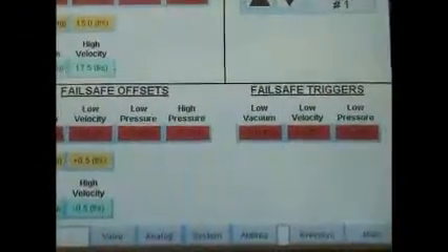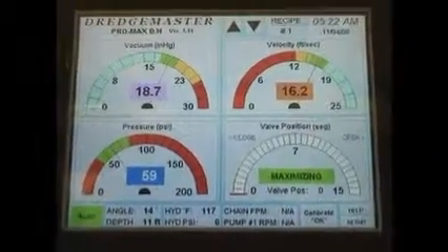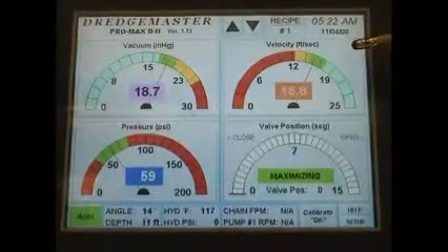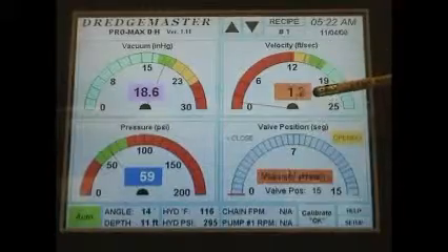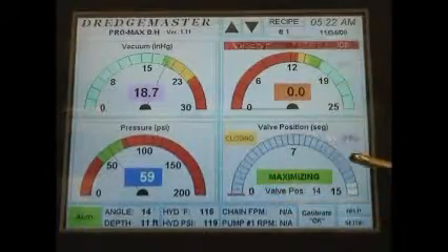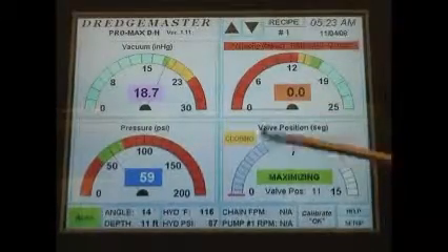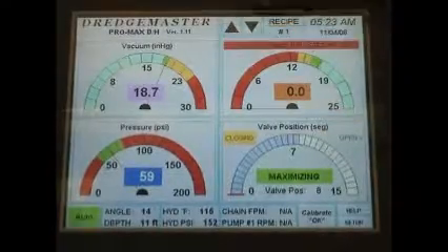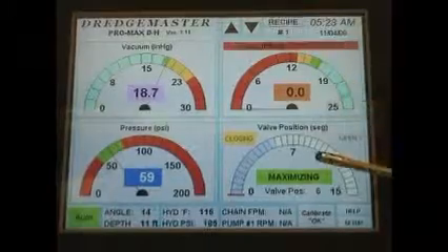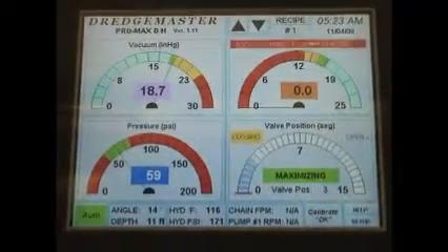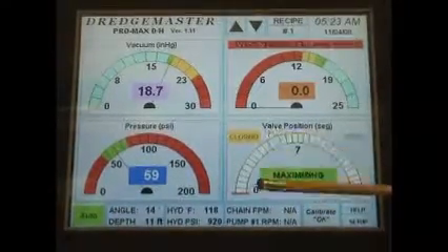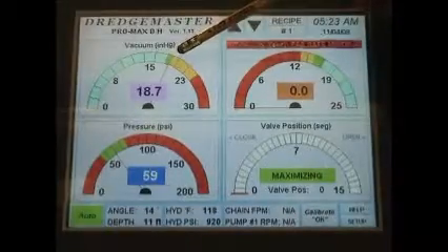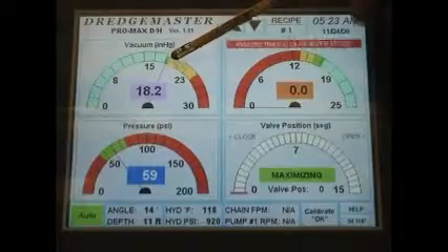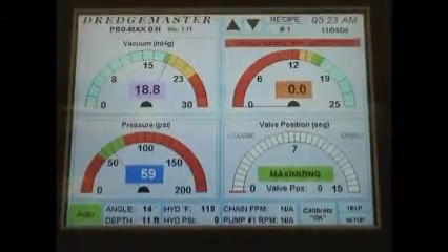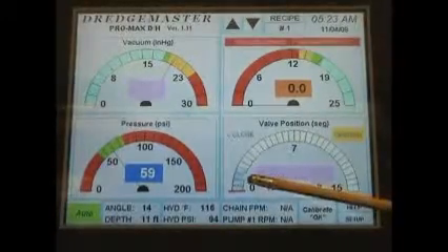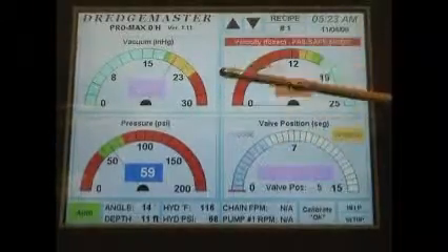So if we go to our main screen and demonstrate this, our vacuum meter currently is working, but let's make an assumption that our vacuum meter now has failed. We're below our 3 feet per second. The valve first opens itself up because it thinks we've got a problem, and then it says, okay, we're in what we call velocity fail-safe mode. So the valve closes itself back up, and let's allow the valve to fully close, which it has. Now notice our green zone has narrowed up a bunch. We are now opening up this valve at 19, remember, instead of 20. So the valve, let's say our vacuum gets to 19 and above, you can see we are stepping the valve open and closed, even though our velocity meter has failed.